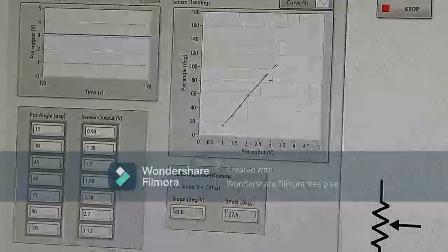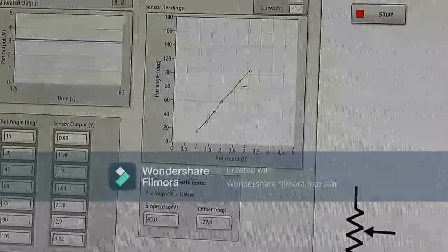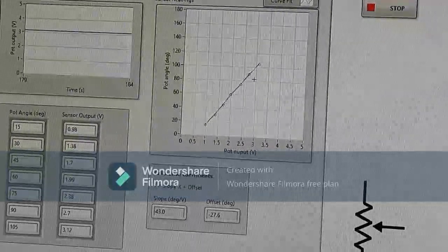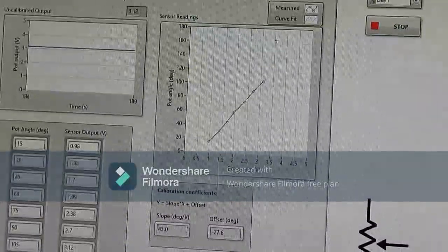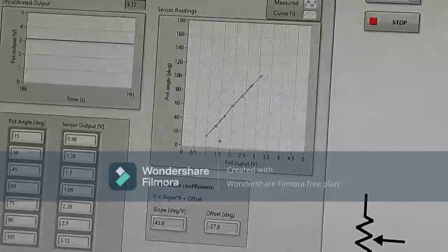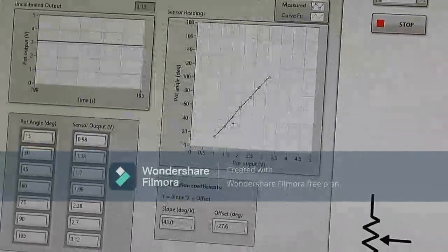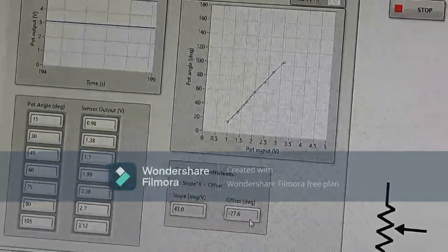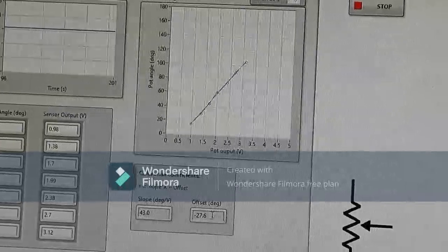So this will occur because once you rotate the knob and place it to the particular position, you might not get the exact point. Now if you see the graph very carefully, it is almost merging with the red line. Previously the error margin was larger, but let's check for this one. Fine. So we get the slope here as 43 and offset minus 27.6 degrees.